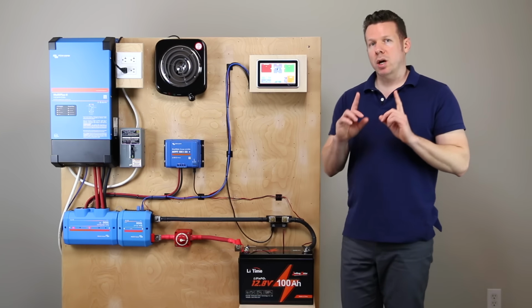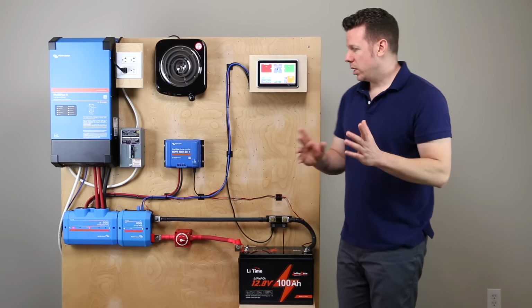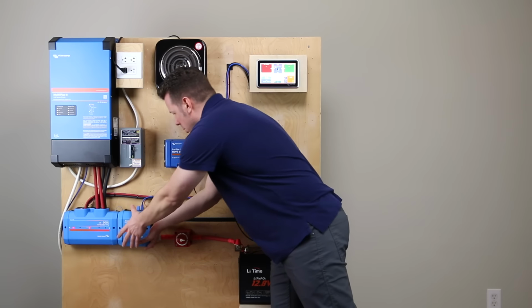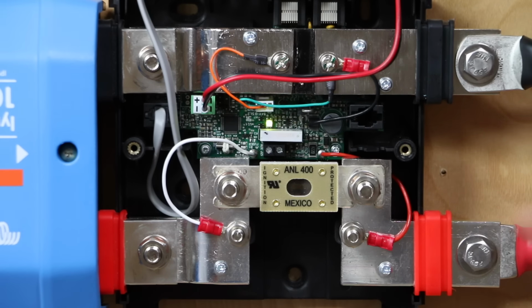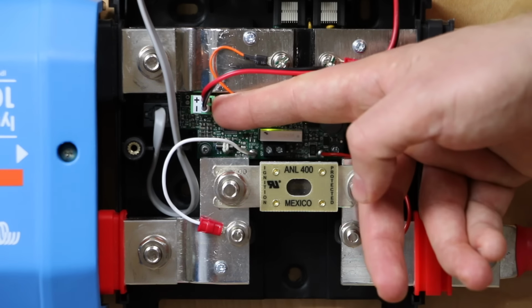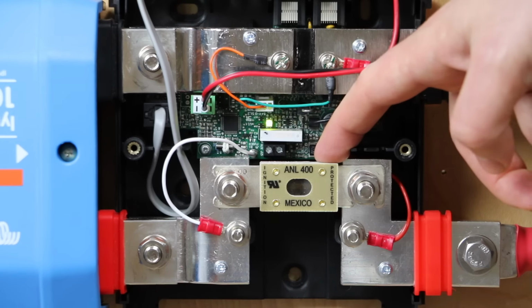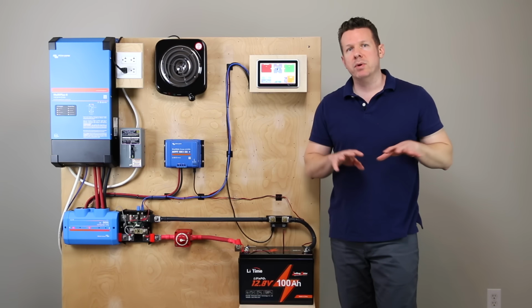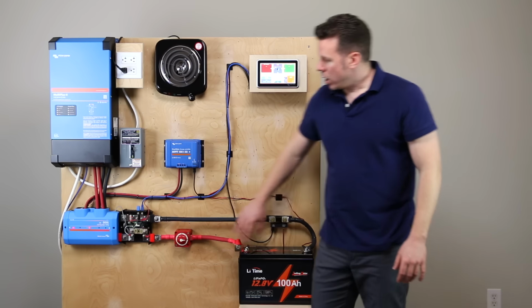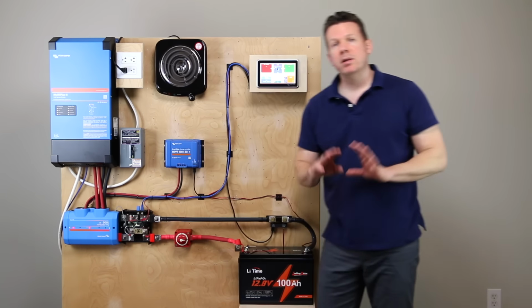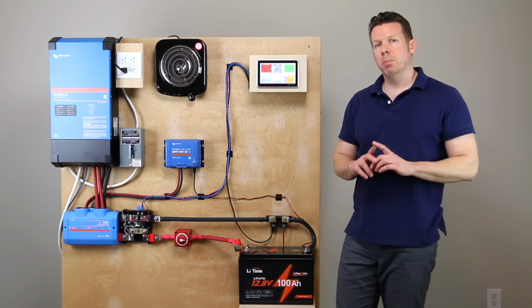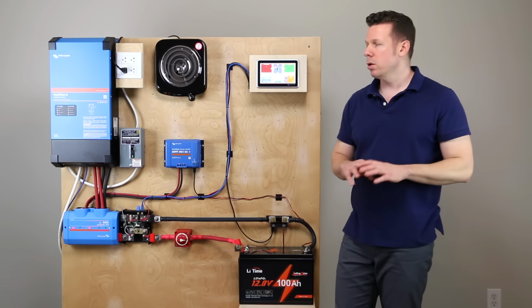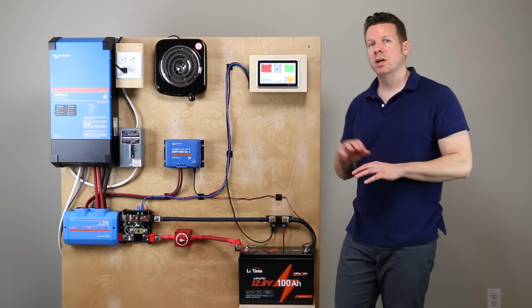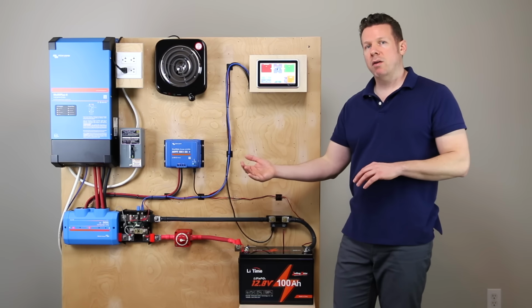I do want to mention a couple of additional features with the Lynx Shunt. In addition to the temperature sensor, which you can see here, it also has a spot for a main fuse. So even if you have little fuses on each battery coming in, when it runs through the Lynx Shunt, you can have a main system fuse there, and it will also report whether or not that fuse is blown to your GX device, and it can set off an alarm.